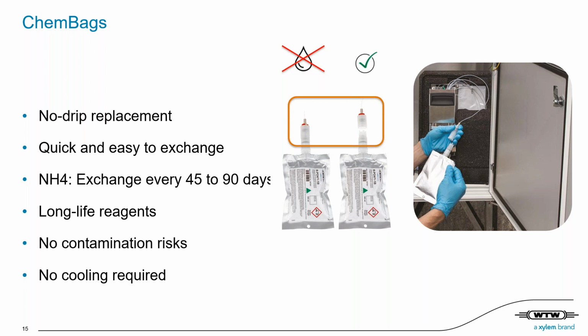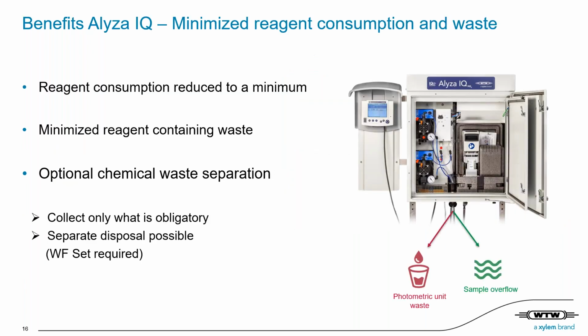challenges for you. The new disruptive MultiPort valve technology, as mentioned before, reduces the reagent consumption of Alyza IQ to a minimum, with less than 2 milliliters per reagents per day at a 10 minutes interval. This extremely reduced reagent consumption also results in a dramatic decrease in chemical-containing liquid waste, with less than 18 milliliters per day. Traditional wet chemical analyzers don't have the option to separate this chemical waste from the overflow, and thus the liquid waste amount is even higher. Fortunately, the Alyza IQ platform offers an optional waste collection system to only collect what is obligatory, resulting in a further operating cost reduction where charge disposal is mandatory.